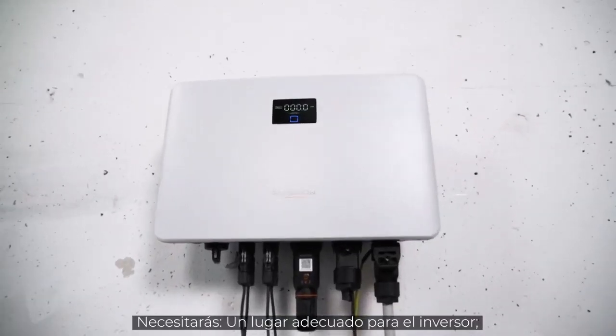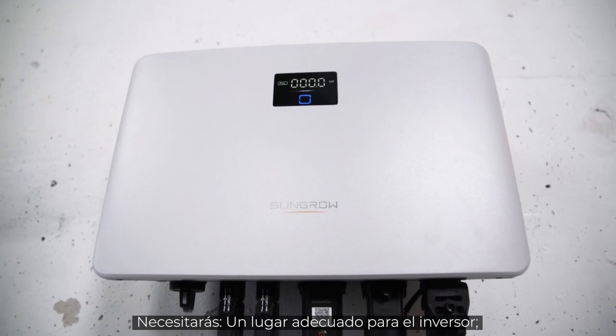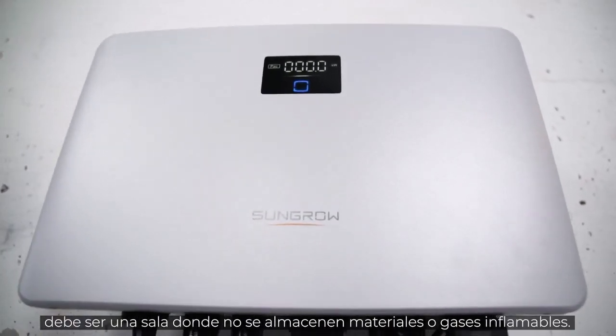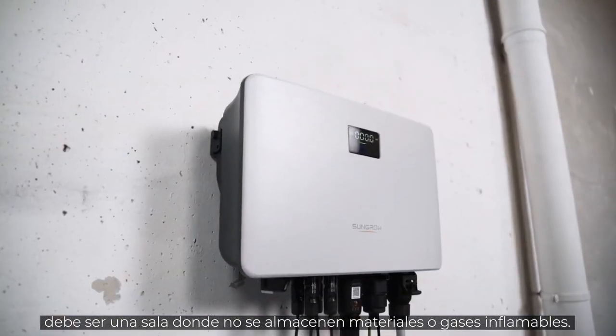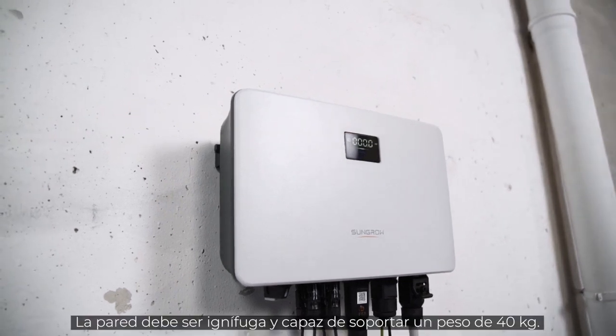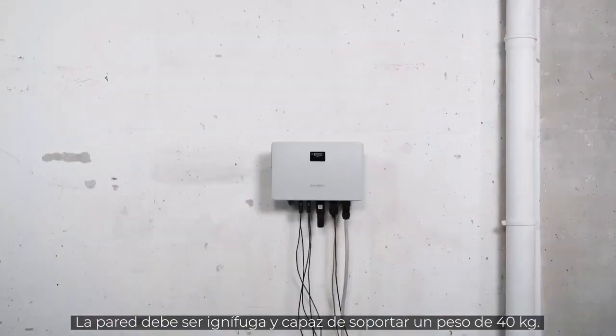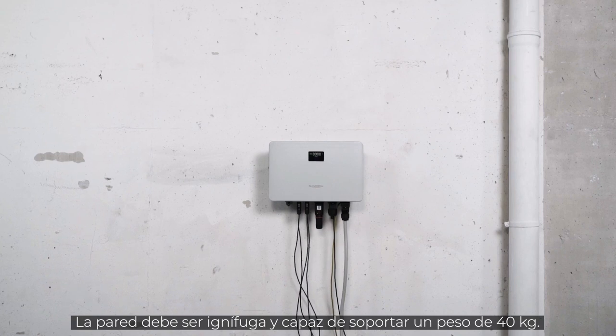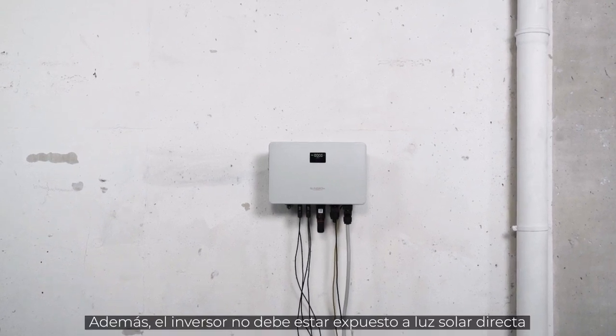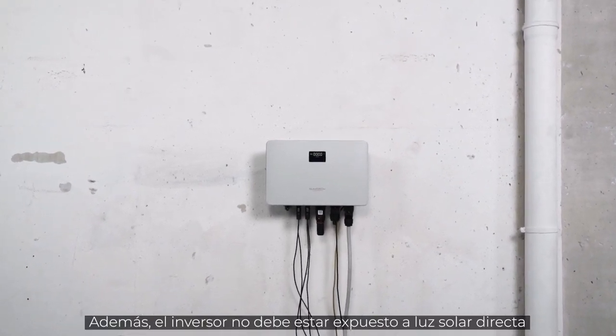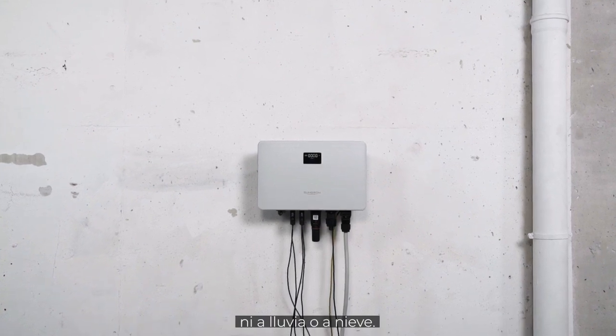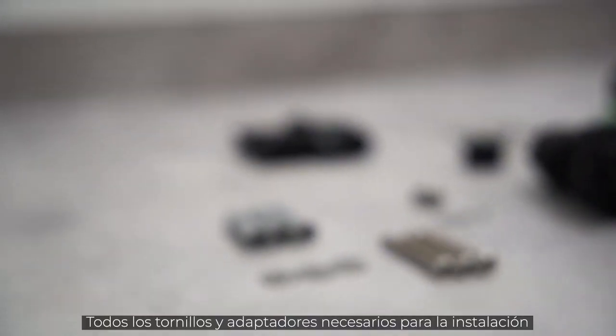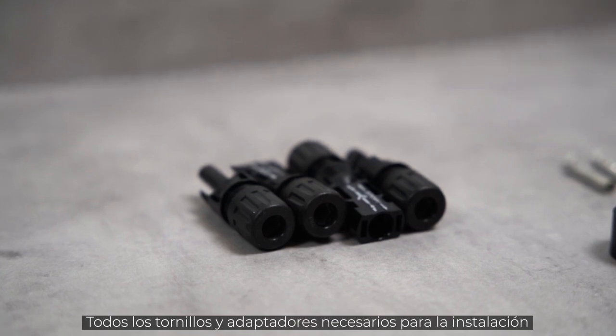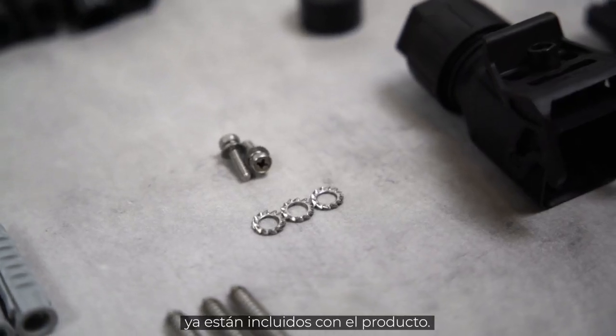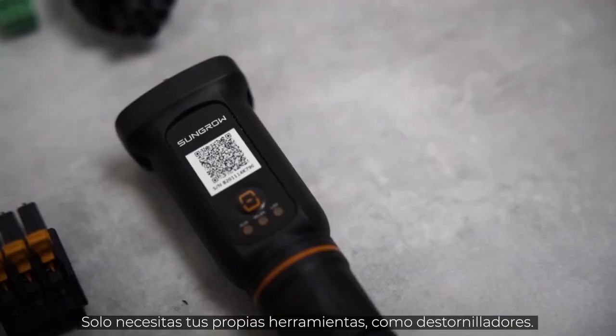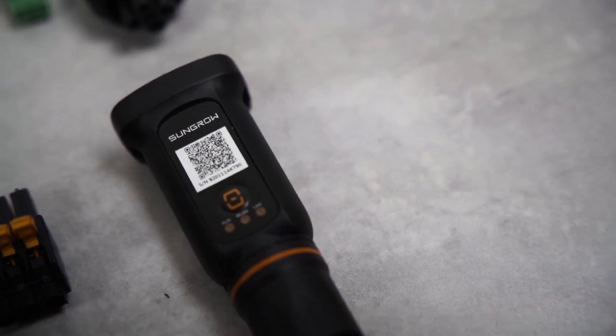You need a suitable place for the inverter. This means it should be a room where no flammable materials or gases are stored. The wall must be fireproof and able to bear the weight of 40 kg. Furthermore, the inverter should not be exposed to direct sunlight, rain or snow. All screws and plugs required for the installation are already included in the delivery. You only need your own tools like screwdrivers.